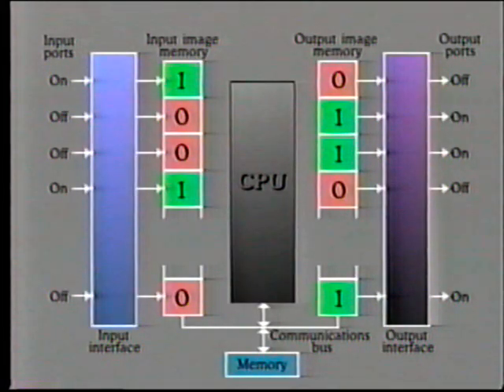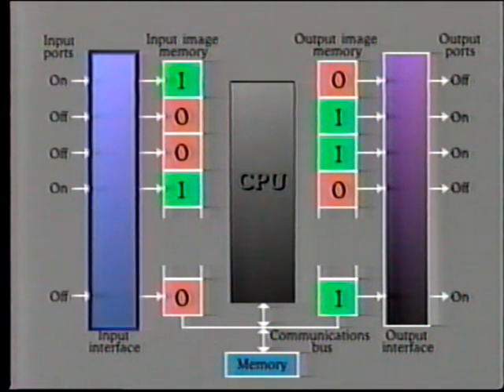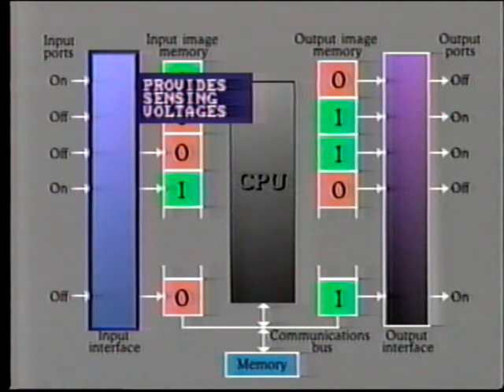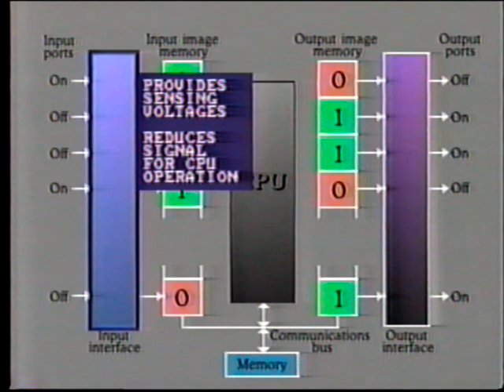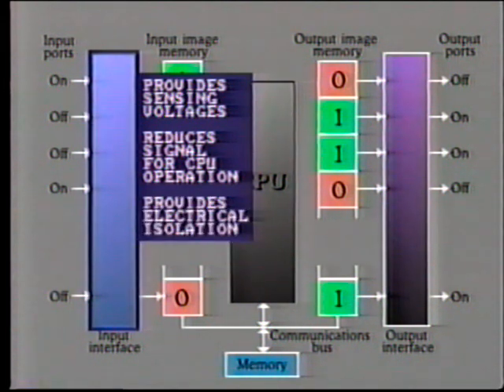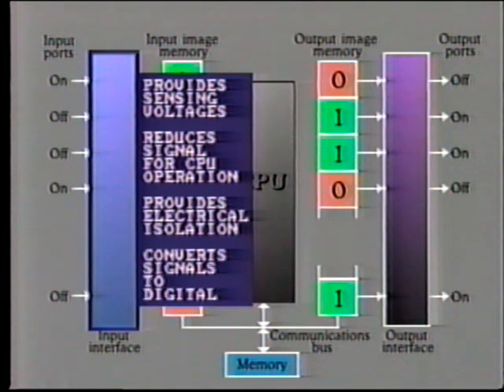The interface is in fact the input module, which sits between the input terminal and the image memory. This module performs several tasks, such as provision of the required voltage levels for sensing and reduction of each signal voltage level down to that required for operation of the CPU. It provides electrical isolation between the incoming signals and the CPU. This is to protect the CPU from spikes and other undesirable external effects. It converts the incoming voltage signal into computer binary language for storage in the image memory.